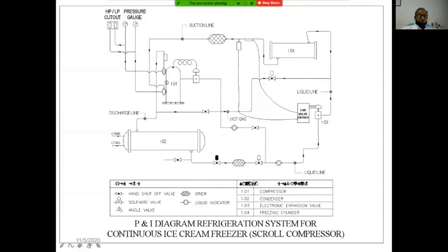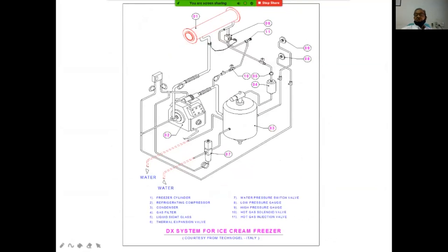This is again the scroll compressor. There is nothing new, it is the same system, but there are some requirements for a scroll compressor when it is going for low temperature and when the discharge is high. It requires some cooling of the scroll compressor. It requires a heat injection, liquid injection system, and that is shown here. This is how it looks in the isometric.